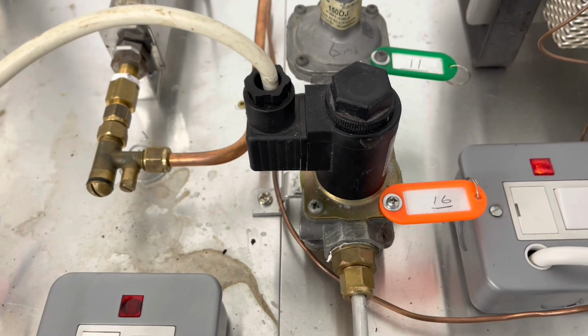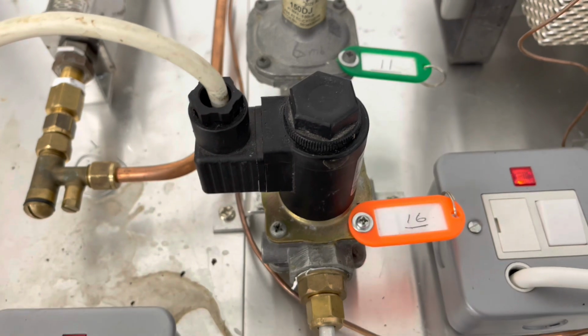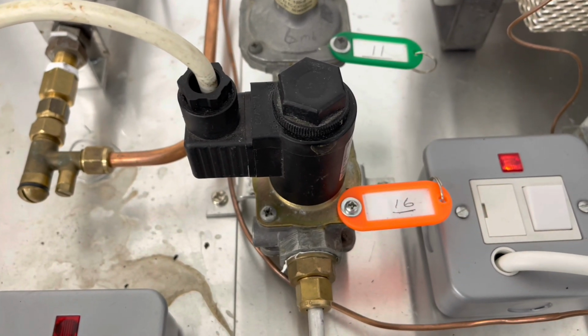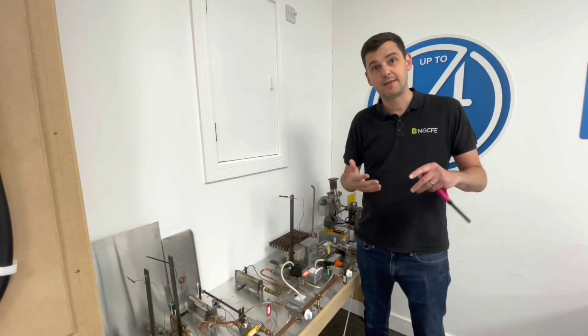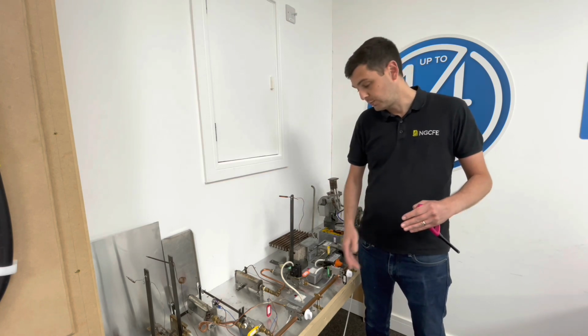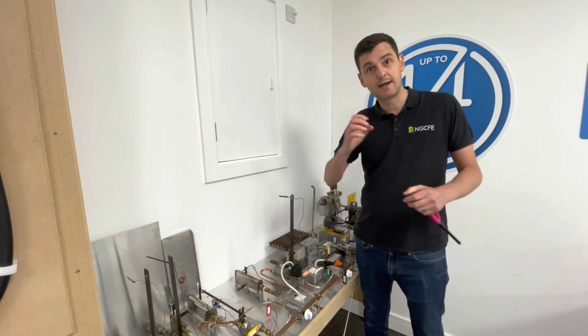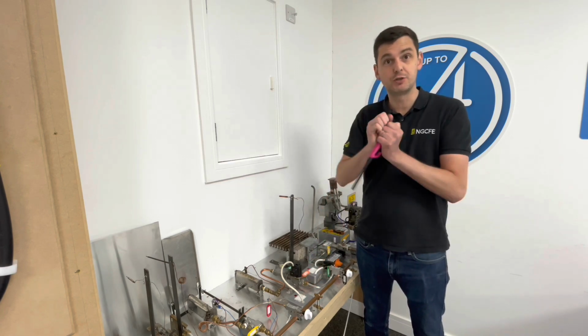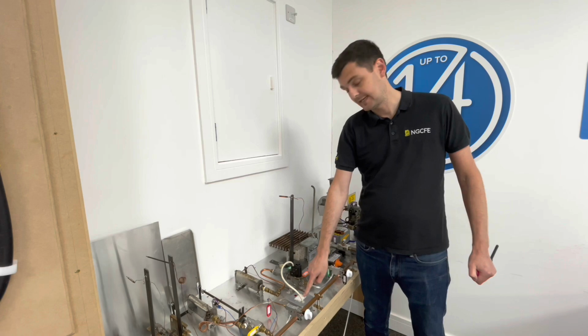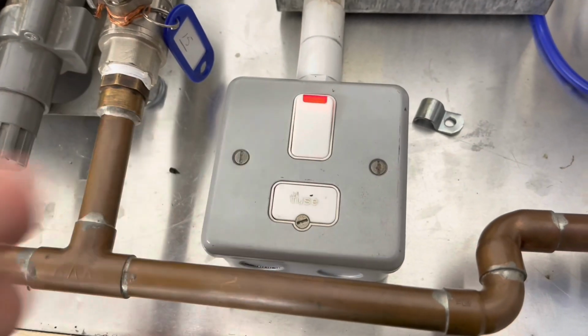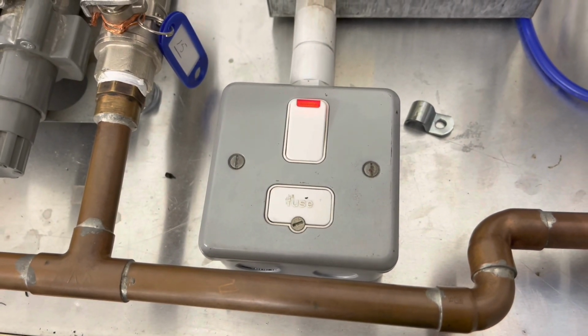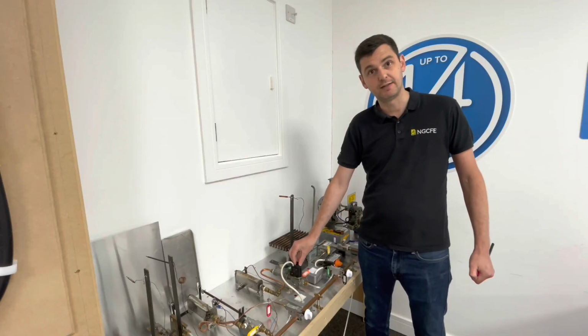This small valve here with the black actuator on top is a solenoid valve. And what a solenoid valve does is it's a valve that again utilises electricity and a magnet. So when we introduce electricity, the magnet energises and it draws the valve up and opens it. So I turn it on now, you'll hear that. Now we've got gas through this solenoid valve.